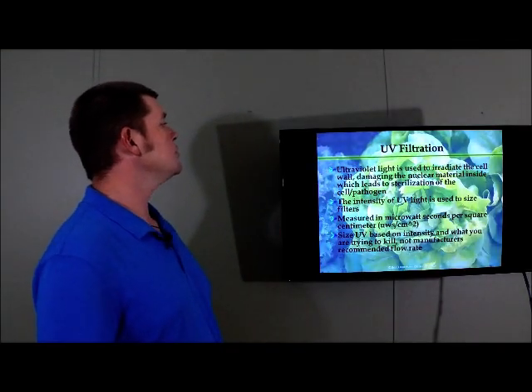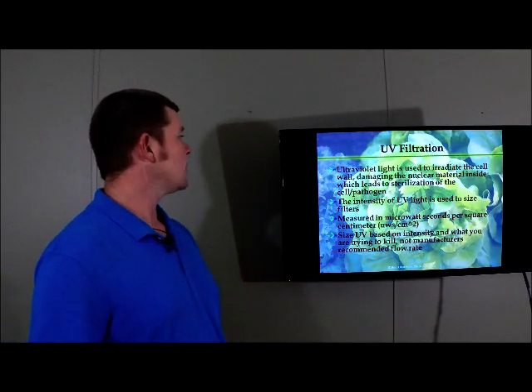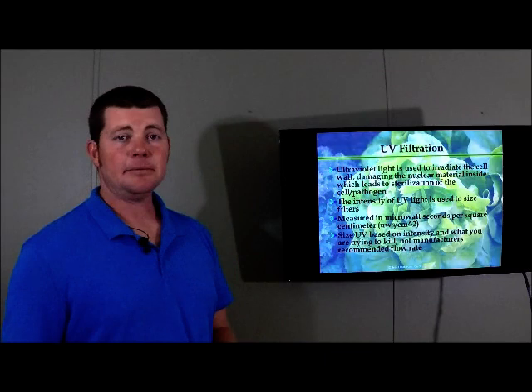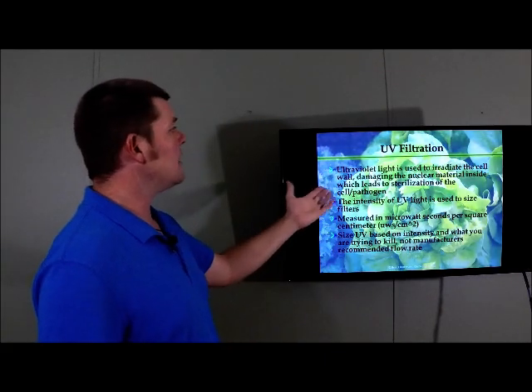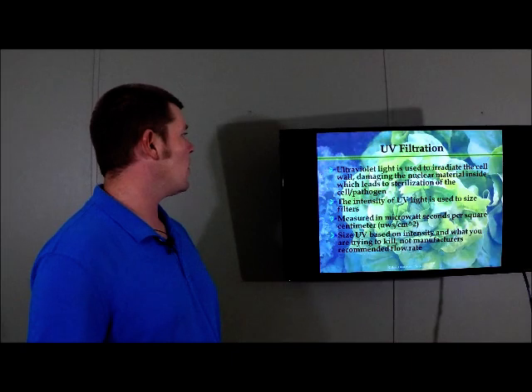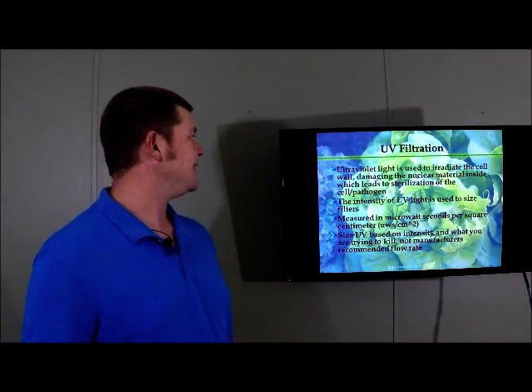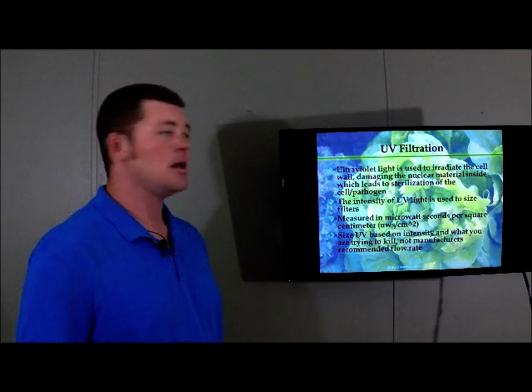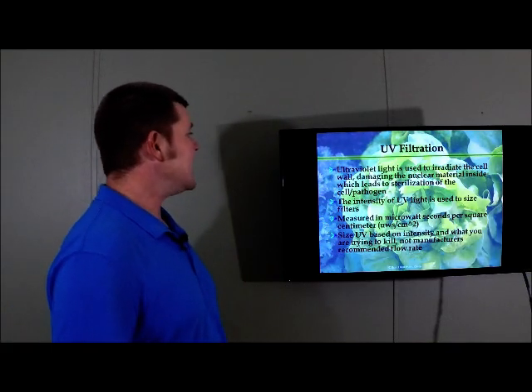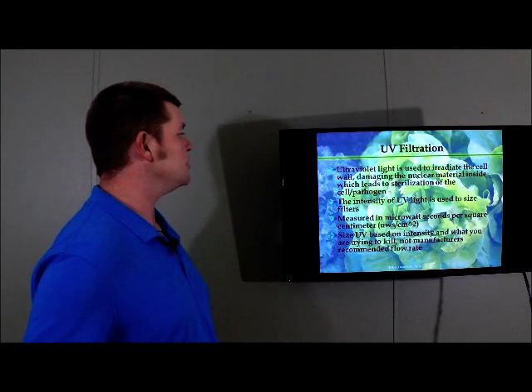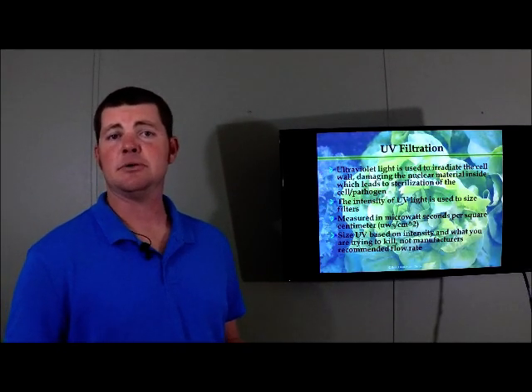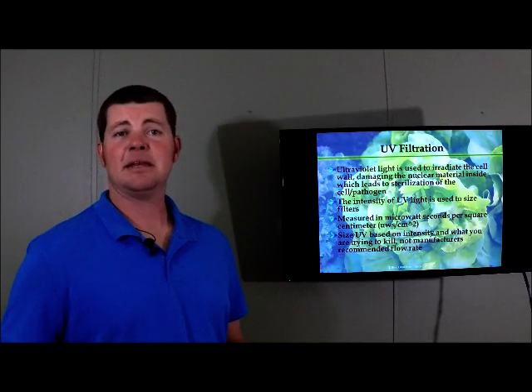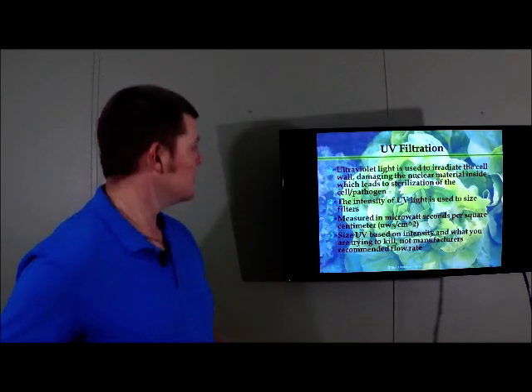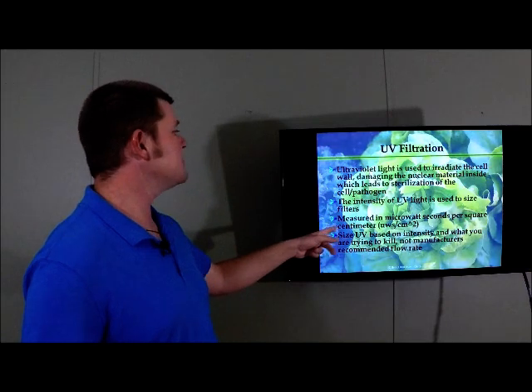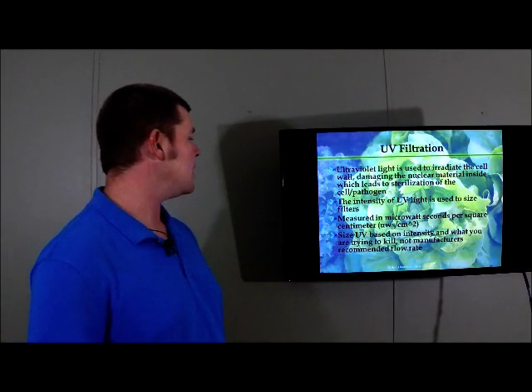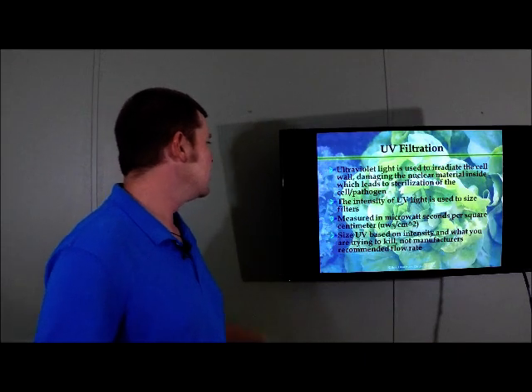We're going to move on now to UV filtration. All right, this is ultraviolet light, if you're not familiar. Ultraviolet light is used to irradiate the cell wall. It damages the nuclear material inside, which leads to sterilization of the cell or the pathogen. The intensity of the UV light is what is used to size the filter. It's basically the dose of ultraviolet light that we're sending into the water. This is measured in microwatt seconds per square centimeter.